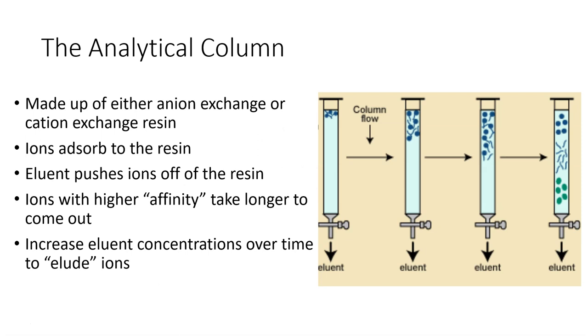The analytical column is the heart of ion chromatography. It's made up of either anion exchange or cation exchange resin. This causes ions to adsorb to the resin, and then eluent pushes the ions off of the resin. So ions with a higher affinity will take longer to come out. And what this affinity means is how stuck to the resin is this ion.